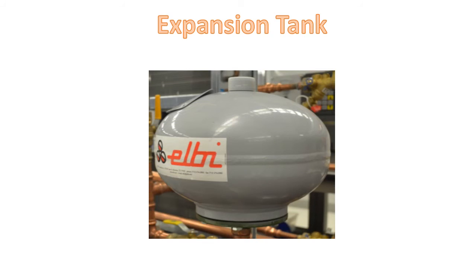Water expands as it heats and contracts as it cools. For this reason, an expansion tank is necessary in the system to accommodate the varying volume of the working fluid. It also helps to maintain a constant pressure in the system.